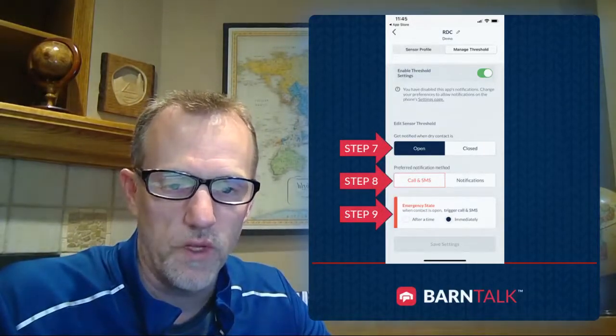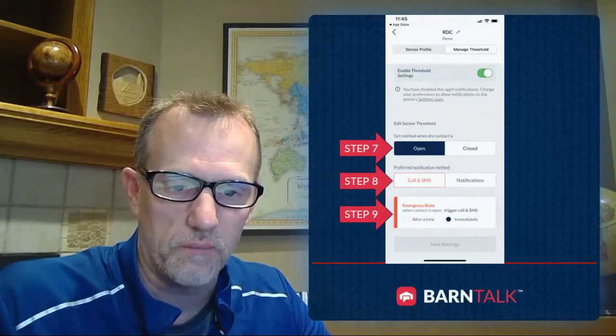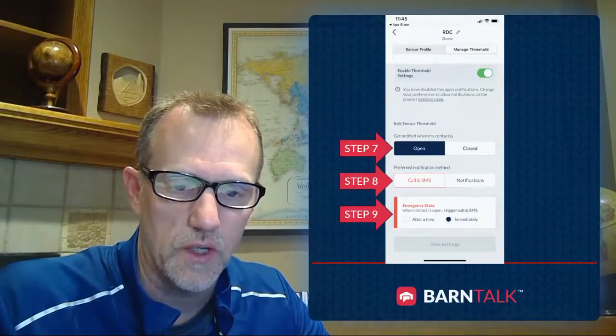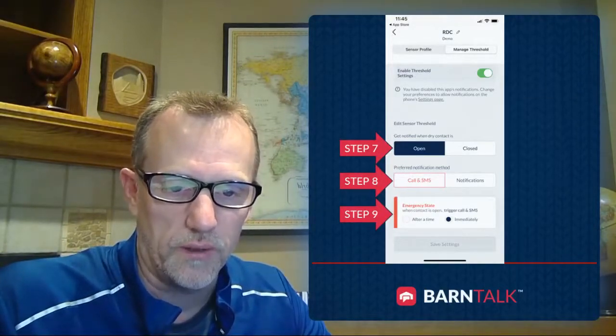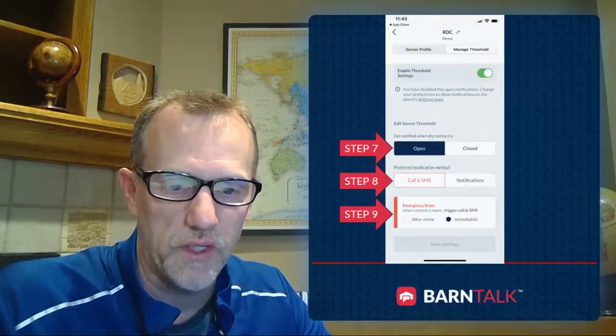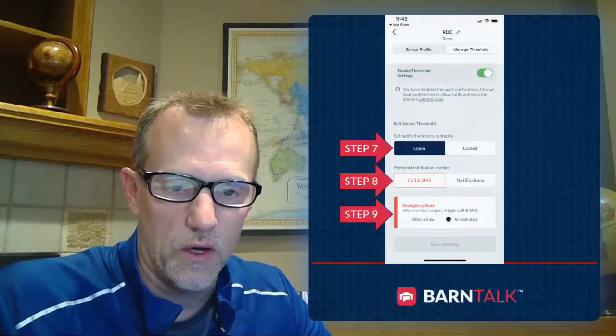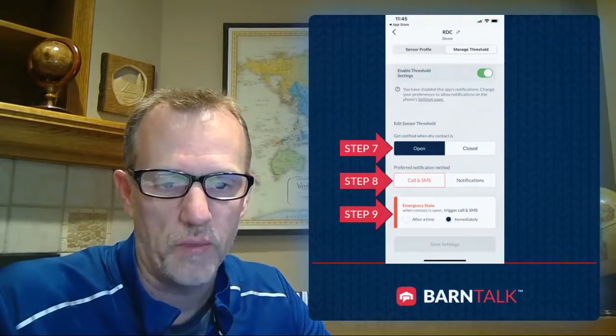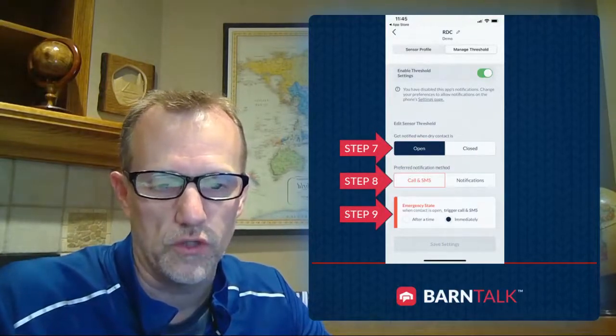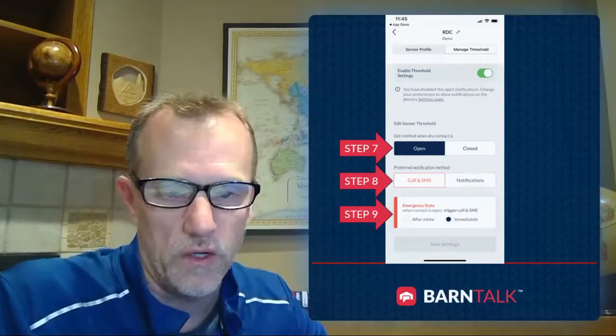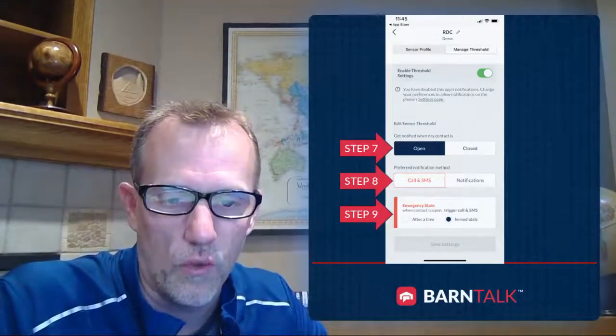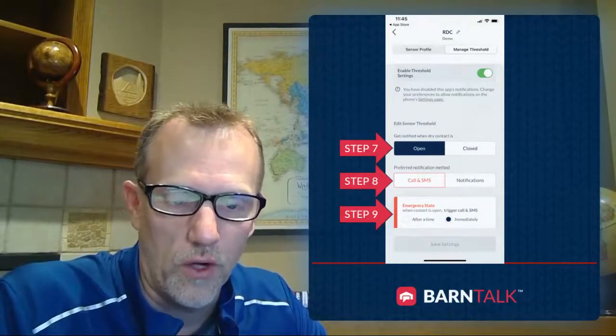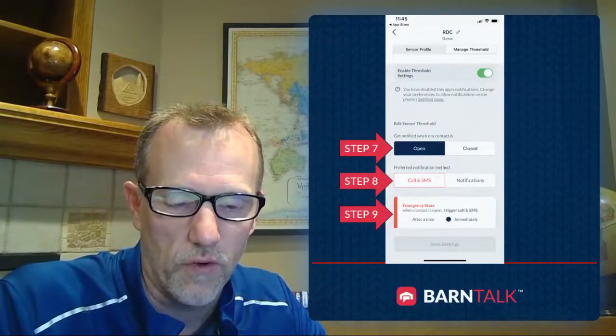Finally, you want to select when to be notified. Because we have call and SMS selected, this indicates an emergency type of alarm, so you would typically select immediately. Or you can select after a time — you can put in how many minutes after the state change you want it to call you. This could be helpful in an auger runtime application where you might want to be notified that an auger has run longer than 60 minutes, for example.